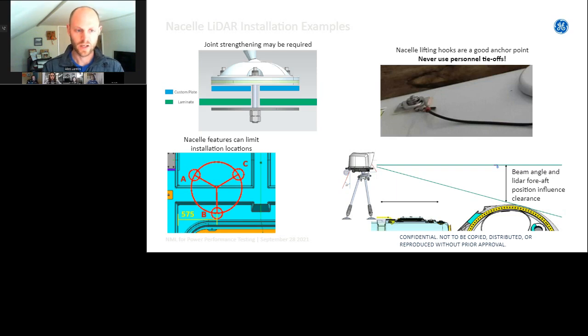So again, engage early. Those custom plates need to be fabricated ahead of time so that they can be installed on time with your campaign timeline. Over to the right here is an example of an anchor point. So for GE turbines, we typically specify the nacelle lifting hooks as a good anchor point. They're rated to lift the nacelle, so they have the strength required to safely attach a nacelle lidar device.